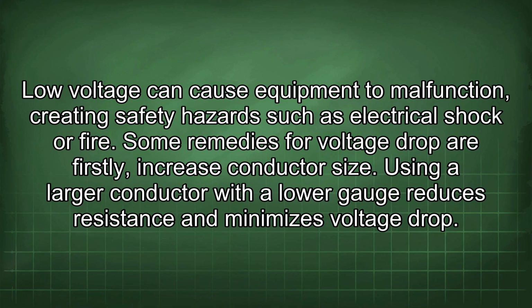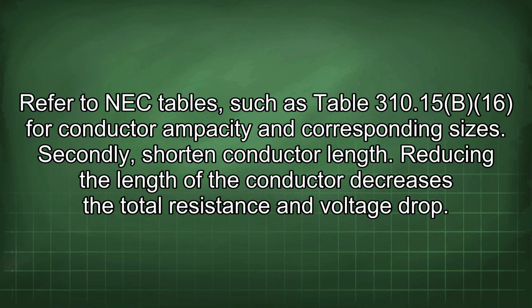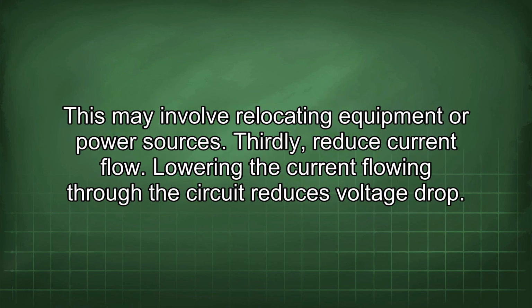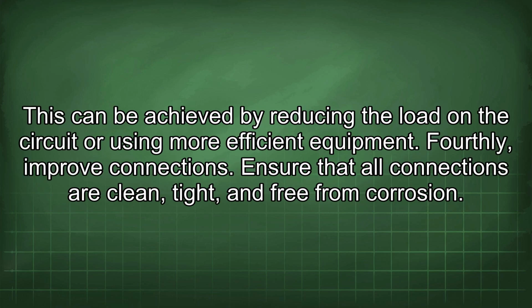Some remedies for voltage drop are, firstly, increase conductor size. Using a larger conductor with a lower gauge reduces resistance and minimizes voltage drop. Refer to NEC tables, such as Table 310.15(B)(16) for conductor ampacity and corresponding sizes. Secondly, shorten conductor length. Reducing the length of the conductor decreases the total resistance and voltage drop. This may involve relocating equipment or power sources. Thirdly, reduce current flow. Lowering the current flowing through the circuit reduces voltage drop. This can be achieved by reducing the load on the circuit or using more efficient equipment.